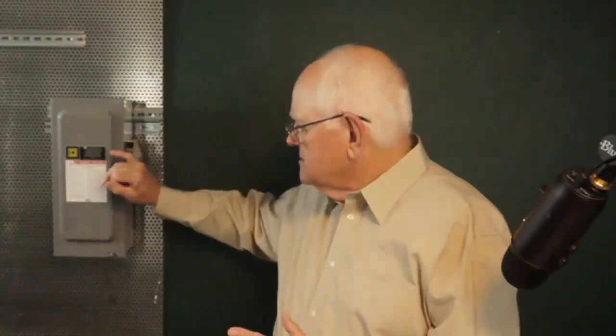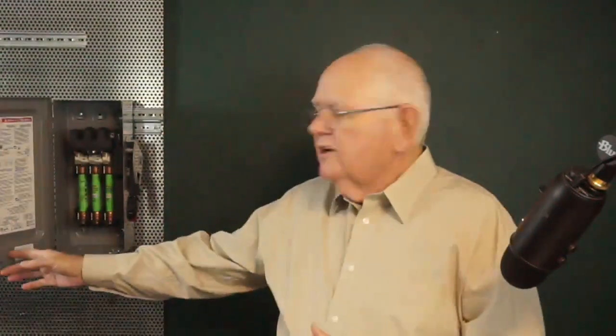Now, protection of the equipment itself is pretty straightforward. We've got to protect against short circuits and ground faults. So, you know, protecting the machine, we've got what? This is some Article 240 stuff, isn't it, from the National Electrical Code, overcurrent protection. Fuses and circuit breakers protect against short circuits and ground faults. So we'll use those to protect our machines. Overloads is what we use to protect our motors from when they draw a little bit too much current and start to overheat on us.